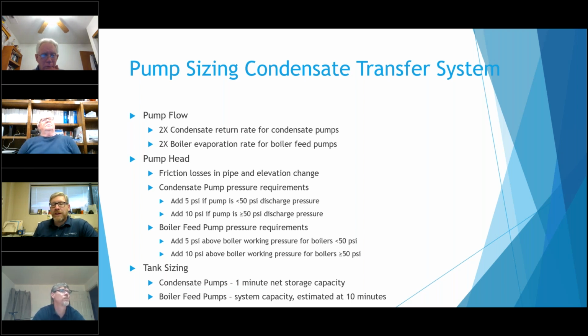The boiler feed pumps, they want to have about a 10-minute storage on that, so the tank is going to be a lot larger. The reason it's so large is that you could get like slugs of water coming back, and you don't want to certainly overfill it because it's all treated water usually at that point, or treated condensate, or it's heated up already. So you want to be able to store some of that as it comes back, because it just varies so much depending on what each little area is doing.